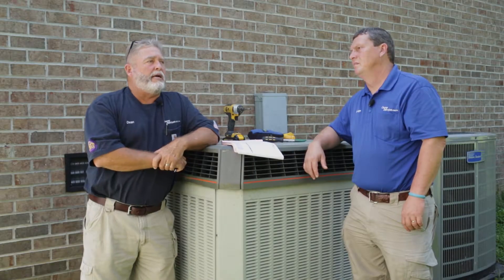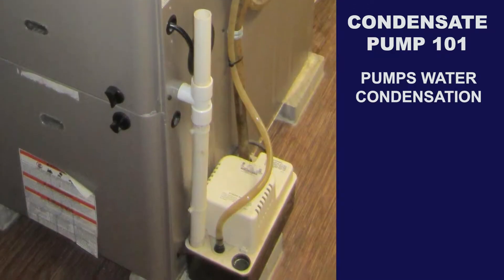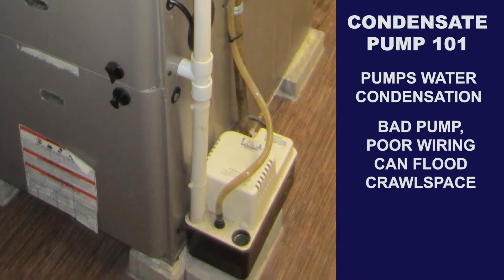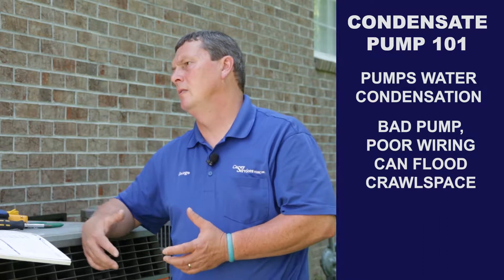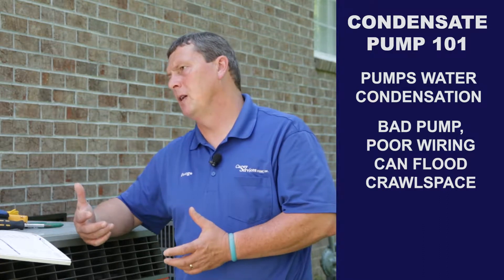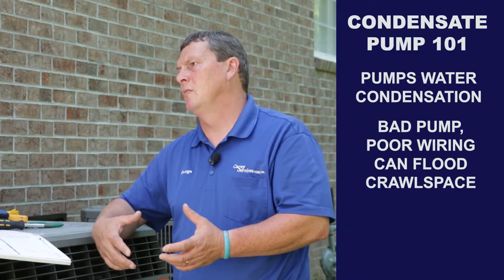Sometimes you can't get drain lines off air handlers, so they have to use condensate pumps. The condensate pump has some safety wires. We've seen condensate pumps go bad and water just fill up the crawl space. If you wire up your safety switches, it shuts something down and lets you know you've got a problem.